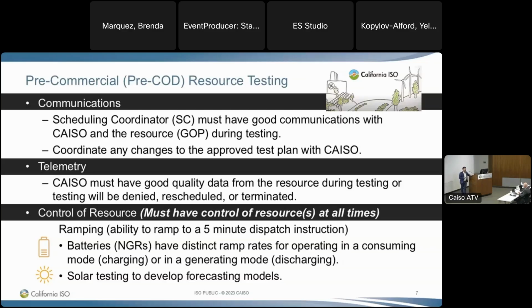Those go on our automatic generation control system, in which they get a 4-second pulse. Sometimes what we find is when they go on regulation, the controllers are programmed to look for a specific indicator coming through ADS. If that indicator doesn't come through, the batteries just sit there and won't follow AGC. So we'll reach out to the site and say, hey, can you put your resource on AGC? And they say, we don't know how to do that. Our controller doesn't allow us to do that. So those are just some of the recent things that we've seen.